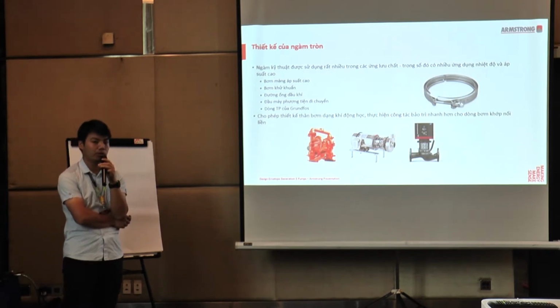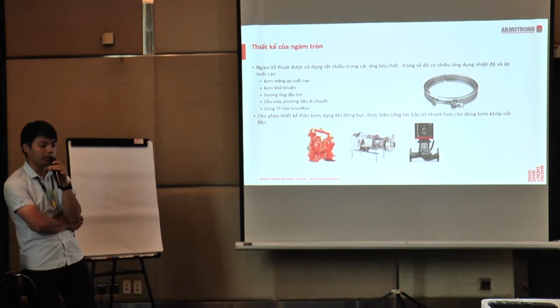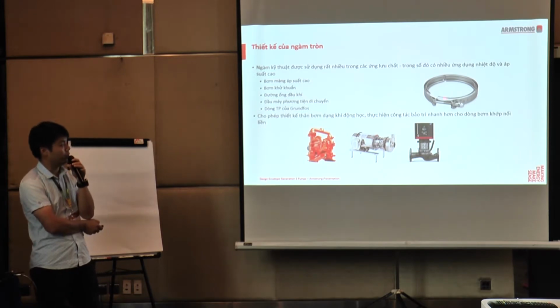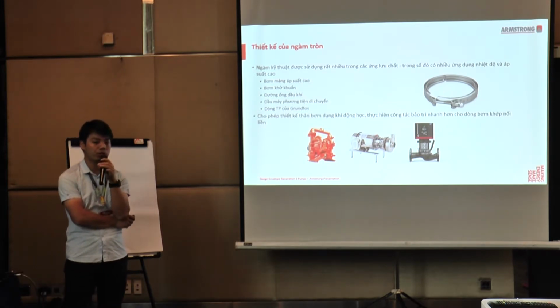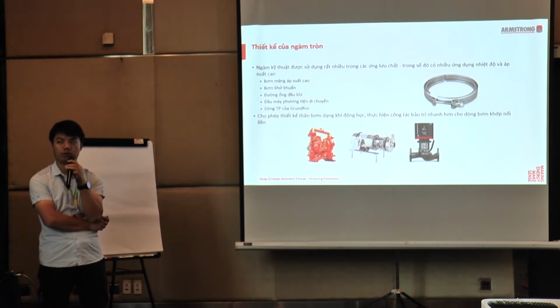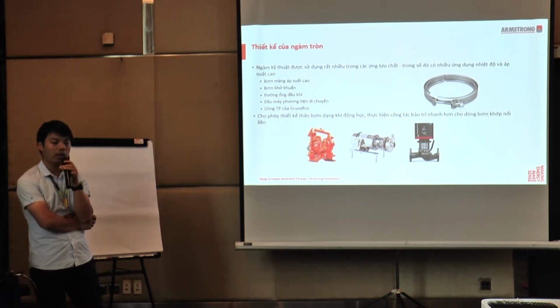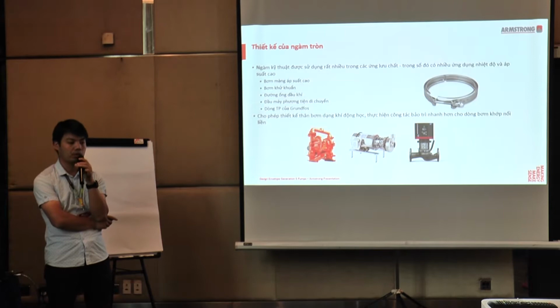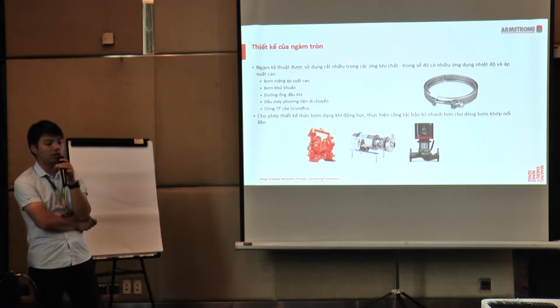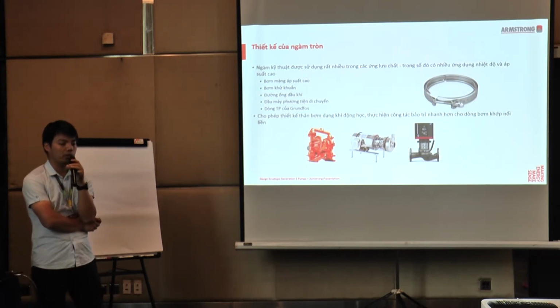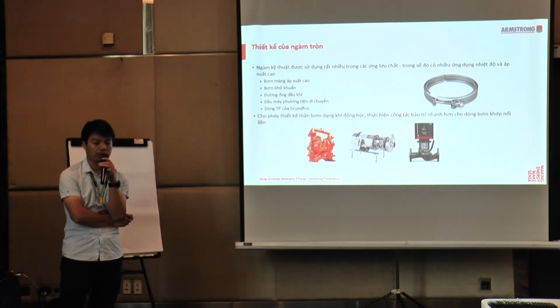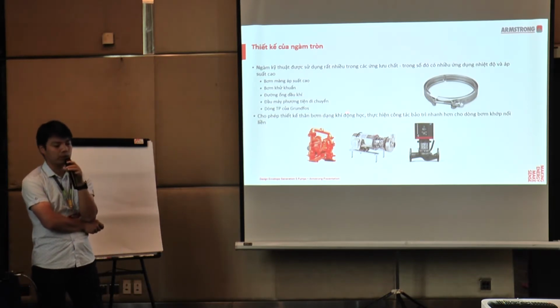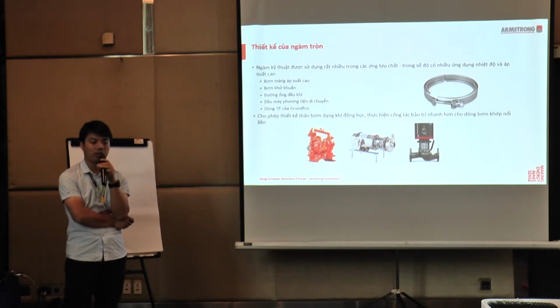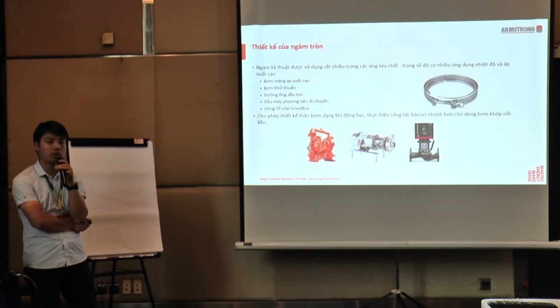Okay, now let's look at the new clamp ring design. This clamp ring design is an engineered clamp used in many fluid applications, and it can bear much higher temperatures and higher pressures. It can be used in air-operated pumps and sanitary pumps and so on. This also allows for a straight-line casing design and quick serviceability of close-coupled pumps.